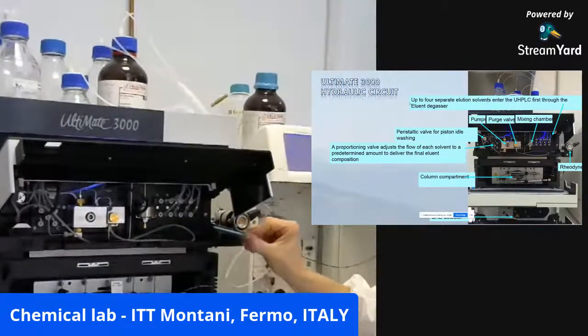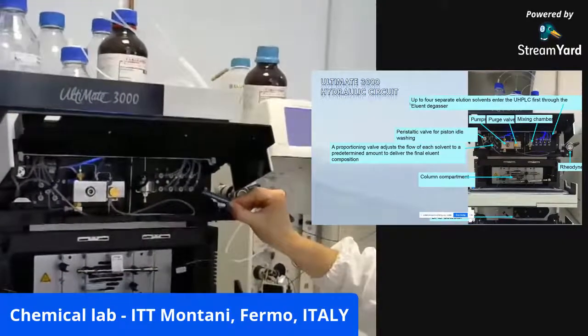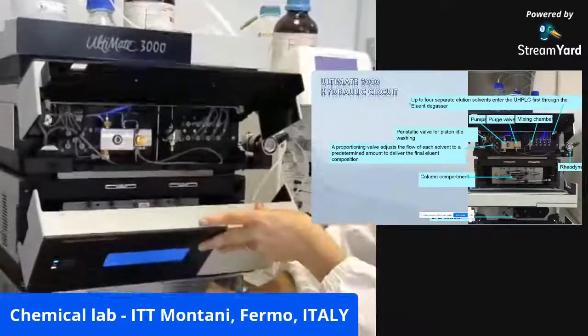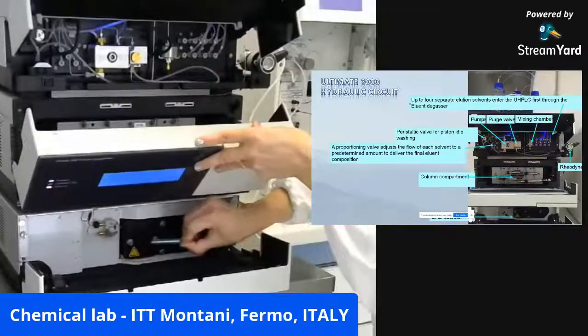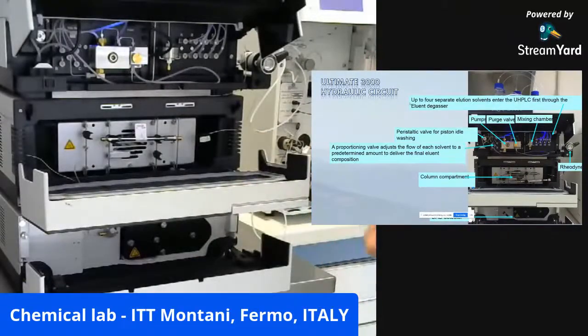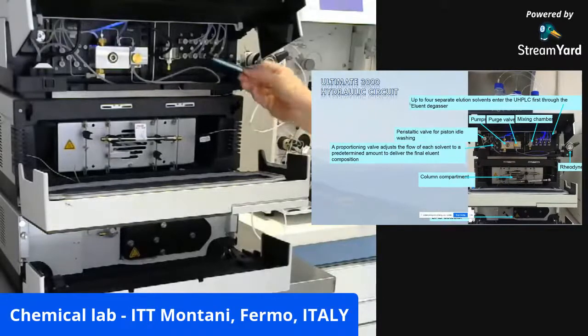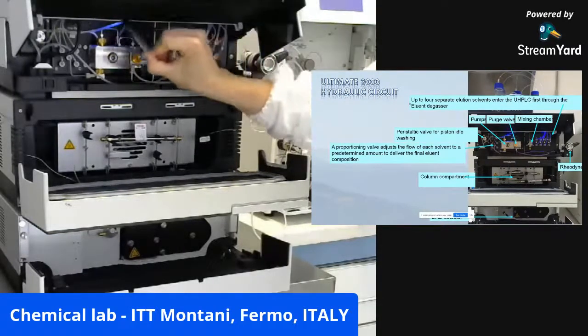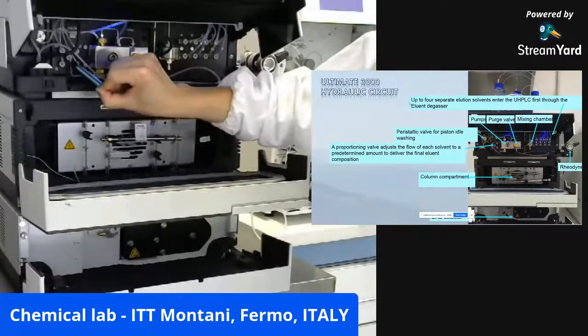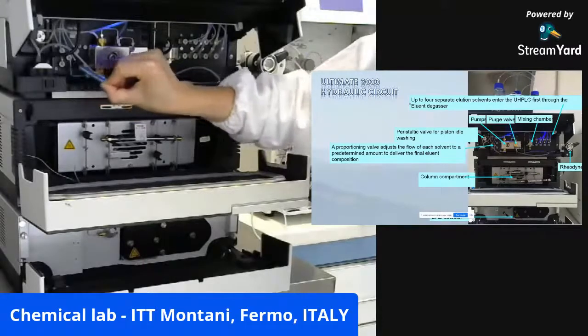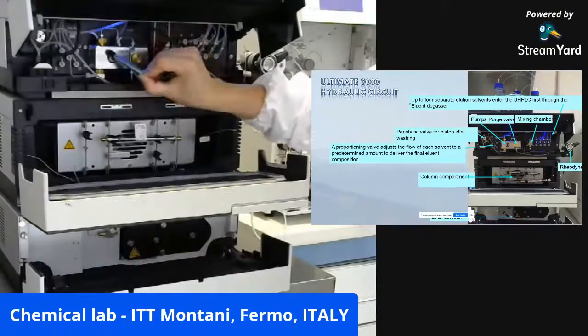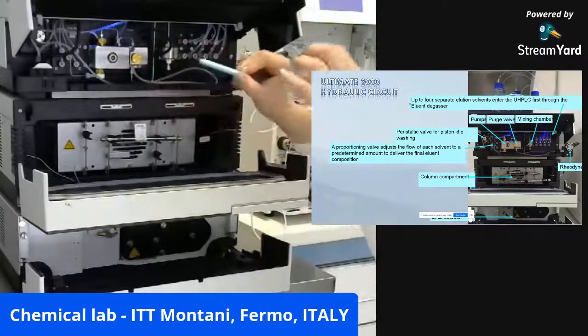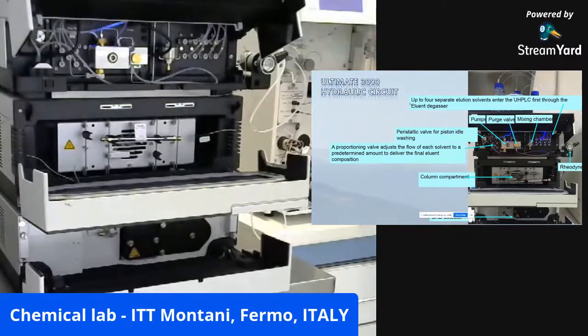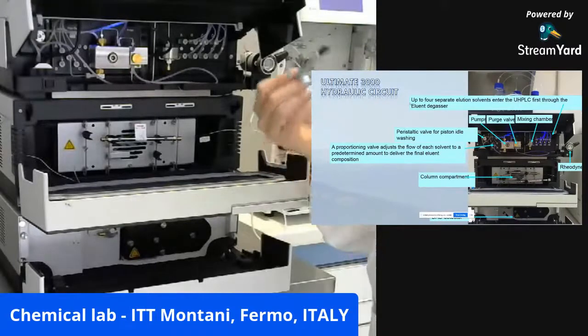Each solvent will be degassed for the same reason, because otherwise at the end of the system here in the DAD, the diode array detector, where the pressure is lower, a bubble may build up and it would be again very detrimental. So after the degasser, they all go to the proportionating valve. You know, this valve has 4 inlets, but only 1 outlet. Why? Because the proportionating valve adjusts the flow of each solvent to a predetermined value, so that the final composition will be the one that we need.